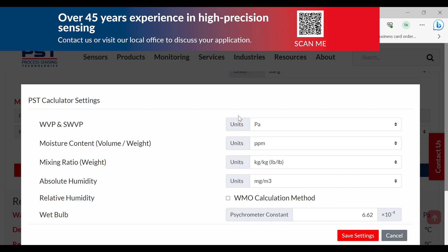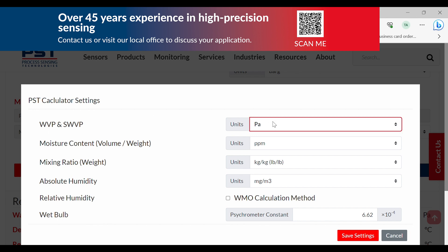In the settings menu, the units for certain parameters can be changed. For example, the water vapor pressure and saturation water vapor pressure can be changed using this dropdown to any of the pressure units listed below. We can also set other options like the WMO calculation method for relative humidity, which forces over-water calculations for below freezing as per the WMO standard.